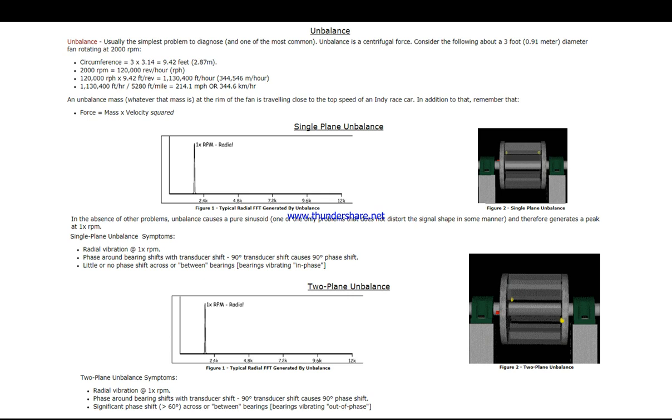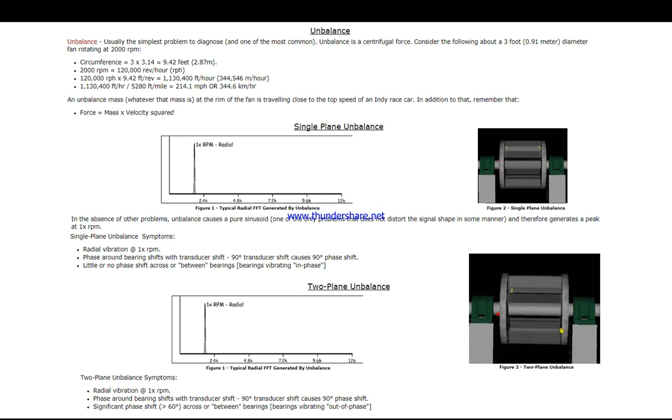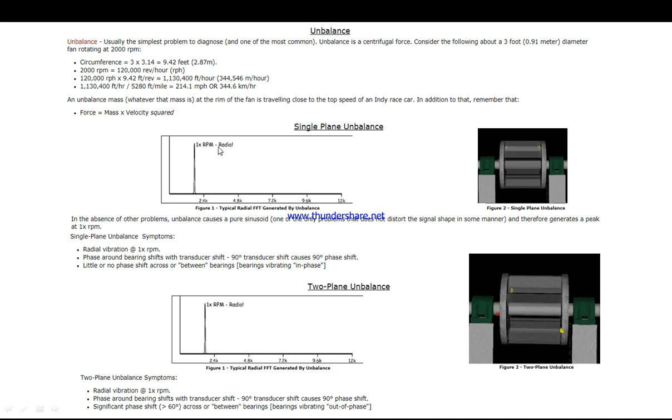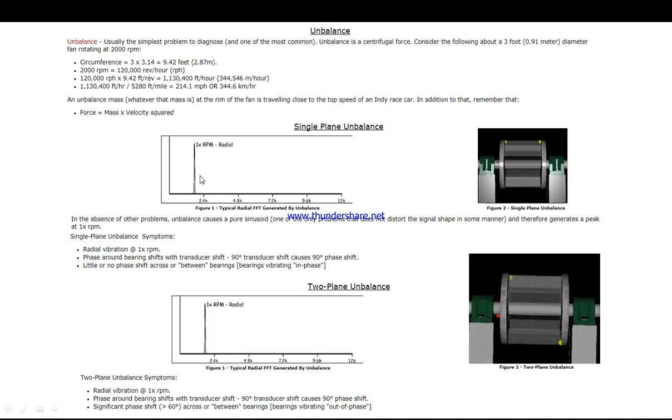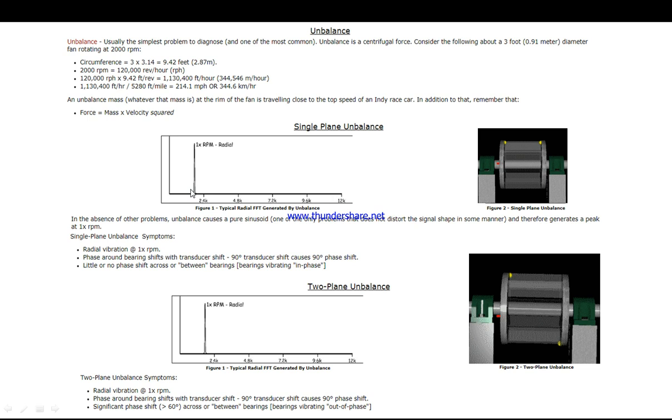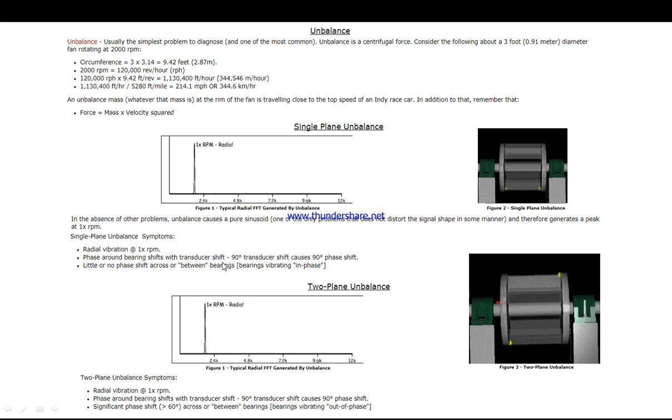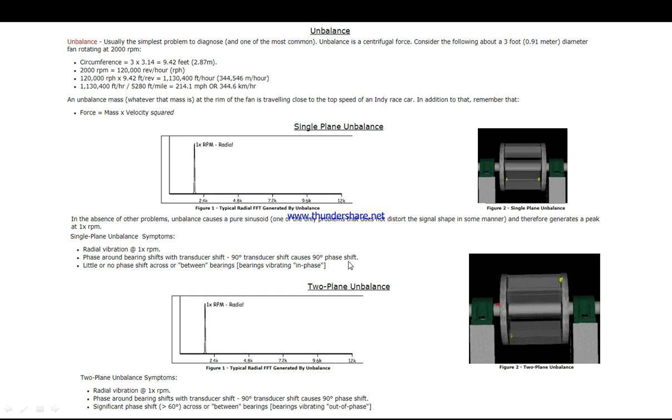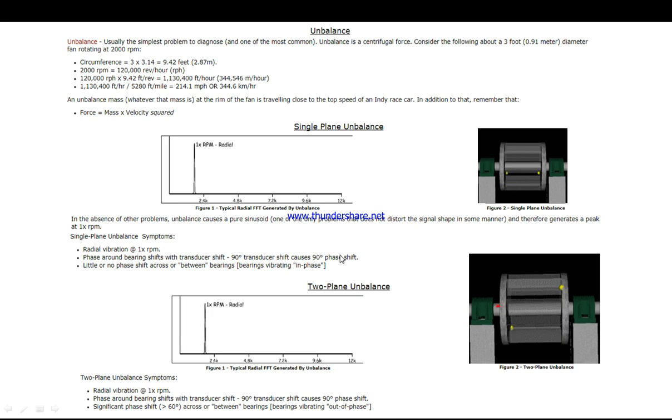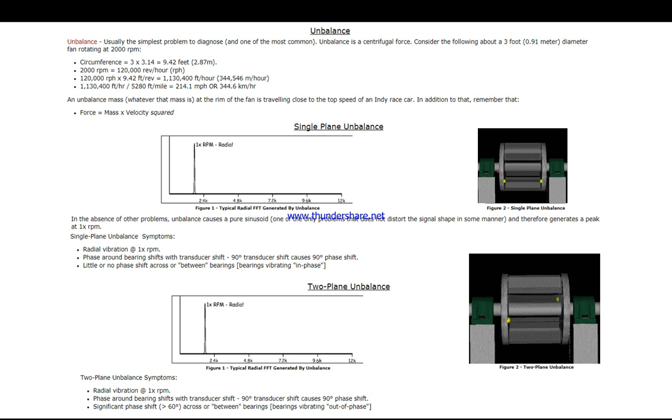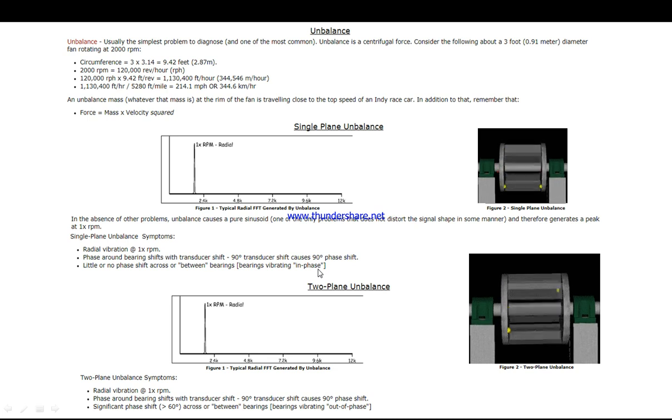With single plane unbalance, the symptoms are as follows: we have 1x RPM (in this example, 2000 RPM appears as 2k). Phase analysis around bearing shifts with transducer shift—90 degrees causes 90 degrees phase shift using the strobe light triggering. It's about 90 degrees, with little or no phase shift across or between bearing vibration and phase.